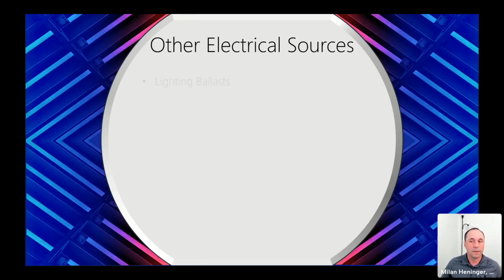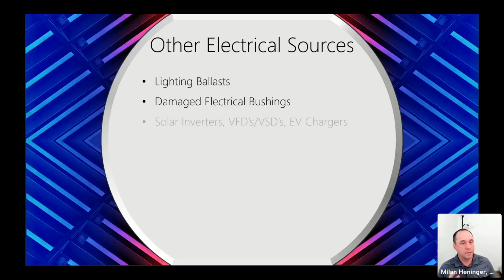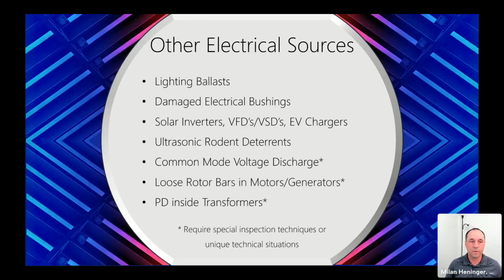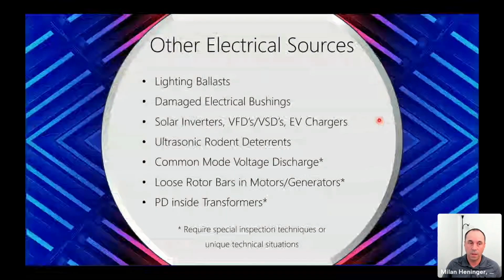Some quick examples: lighting ballasts, damaged electrical bushings, solar inverters, variable frequency drives, variable speed drives, EV chargers. Those are all creating a lot of ultrasound. I have successfully been able to do diagnostics of inverters using ultrasound.